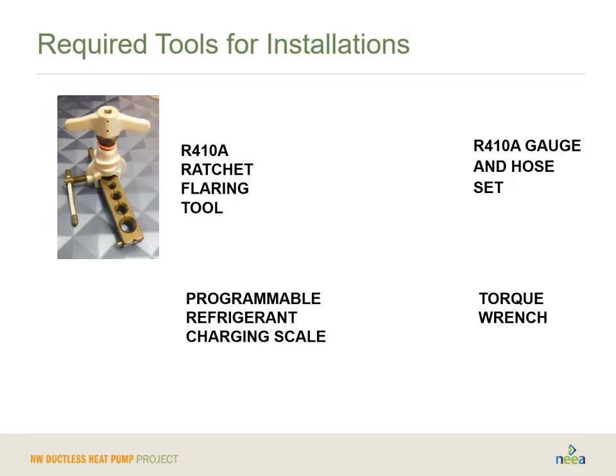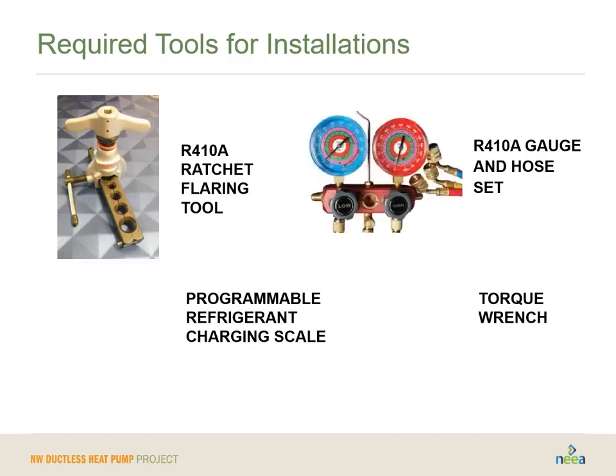You're also going to want to make sure that your R410A flaring tool and your gauge and hose set are specific for R410A. So if you're working on other systems with other refrigerants, go ahead and keep that equipment and use it for other systems, but you really want one designed for R410A for a couple of reasons. One, you want the tools that are most appropriate for the product you're going to be using, but also the oils that are used to make some of these connections can be different for different refrigerants, and we don't want any cross-contamination.